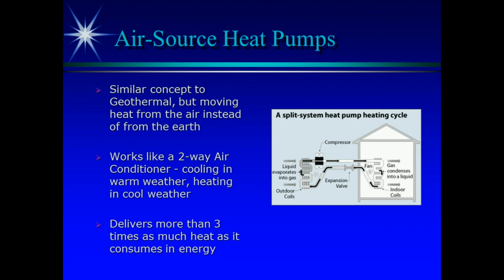That's when we looked at that bar chart and air source heat pumps were 200% as opposed to 400, because geothermal is 50 degrees year round. How hard is it to heat and cool a house if it's a constant 50 degrees 24 hours a day? With the air source heat pump sitting outside, it uses more energy in the winter to extract the lesser amount of energy available.